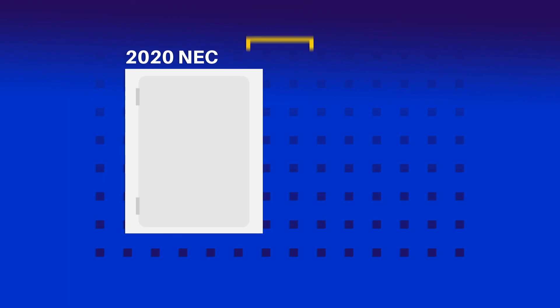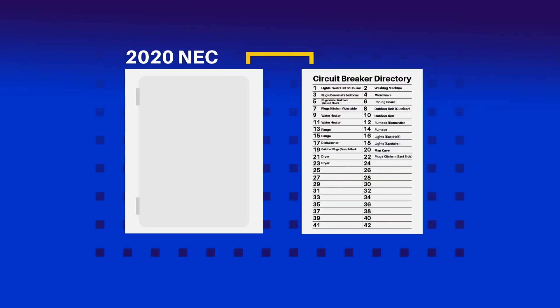The 2020 edition of the NEC may see a significant change by allowing the circuit directory to be placed next to the panel board, with location approval to be specified by the authority having jurisdiction. This is a big step toward a safer and more improved work product. It also makes it easier to coordinate maintenance and inspections of panel board installations.